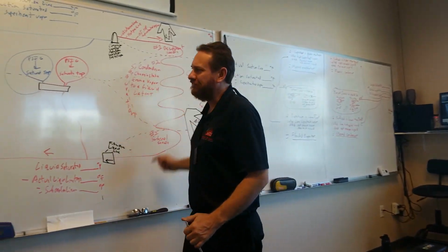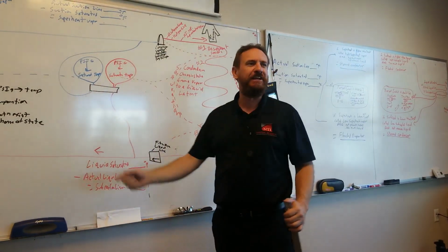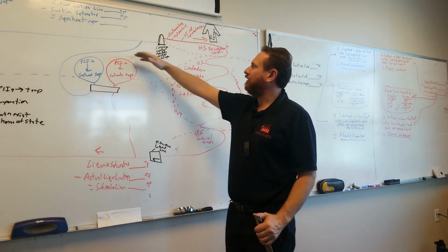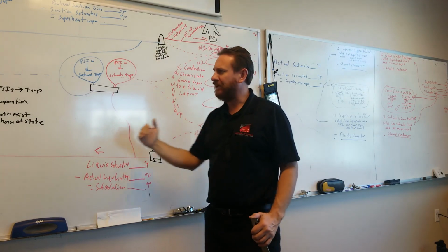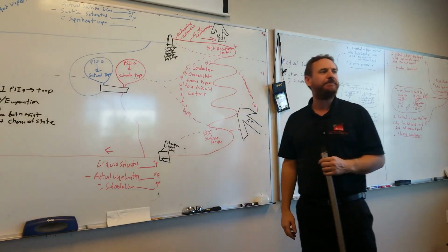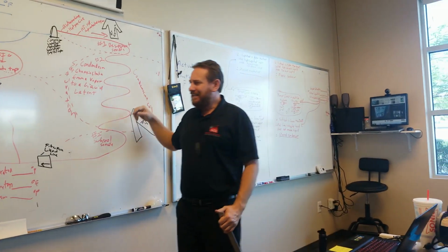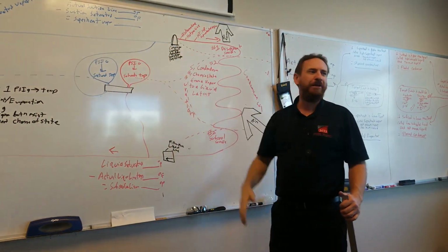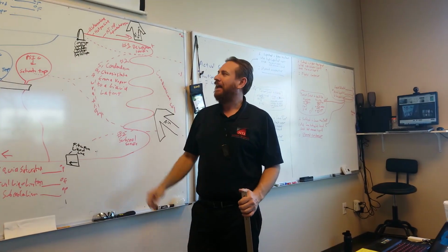It takes about 15 minutes for this refrigeration cycle to get up and running. When it is running, I have to bring in low pressure vapor, pump out high pressure vapor, get this pressure built up, get that pressure dropped, get the airflow moving, get everything balanced out. I need oil return, and the oil flows with the refrigerant to get back to my compressor. Right? It takes a little bit of time.